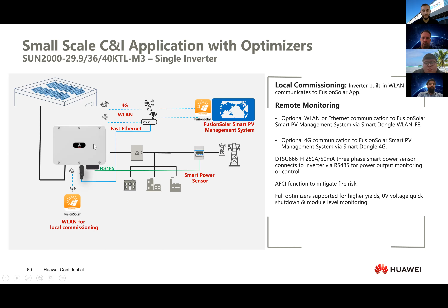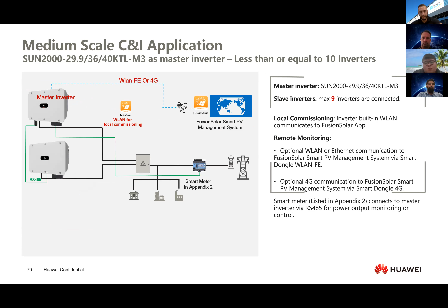You can use the 4G dongle, WiFi dongle, FE dongle, and you can connect a Huawei meter into it, as well as the third-party UPM209 directly into it. And if you have slave inverters, you can use them in conjunction with it too. So you have a UPM209 connected directly into the 29.9, 36, or 40, and slave inverters, 2, 3, 4, whatever. So you can see the smart logger is being eliminated from the solution.